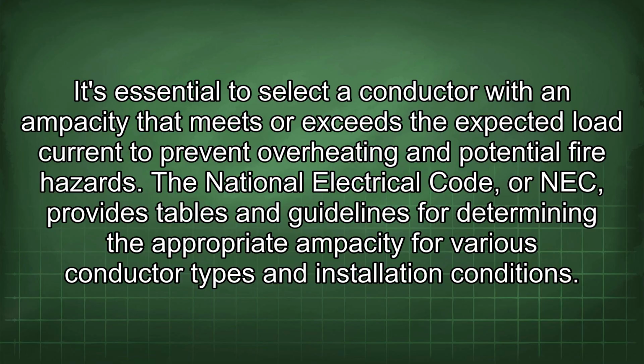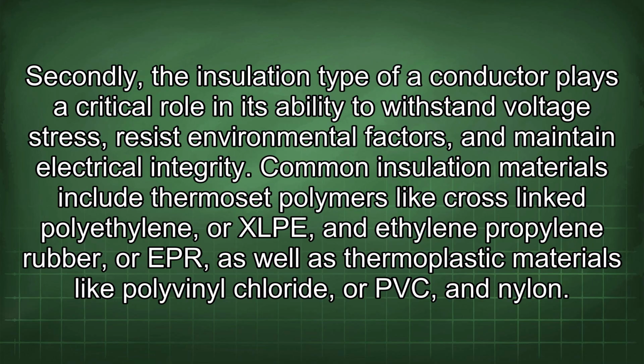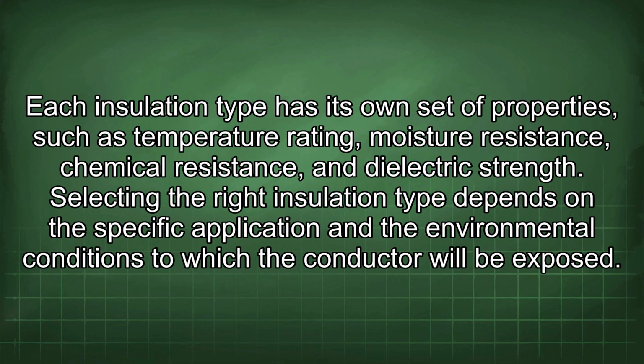The National Electrical Code, or NEC, provides tables and guidelines for determining the appropriate ampacity for various conductor types and installation conditions. Secondly, the insulation type of a conductor plays a critical role in its ability to withstand voltage stress, resist environmental factors, and maintain electrical integrity. Common insulation materials include thermoset polymers like cross-linked polyethylene, or XLPE, and ethylene propylene rubber, or EPR, as well as thermoplastic materials like polyvinyl chloride, or PVC, and nylon. Each insulation type has its own set of properties, such as temperature rating, moisture resistance, chemical resistance, and dielectric strength. Selecting the right insulation type depends on the specific application and the environmental conditions to which the conductor will be exposed.